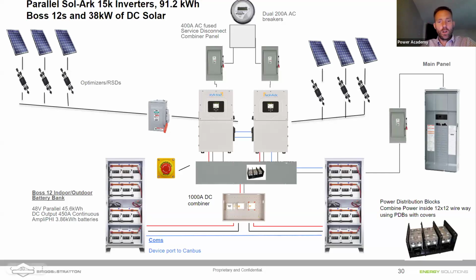I'm showing this here. We've got a 1,000 amp combiner that's here. Briggs & Stratton also offers our own 1,000 amp combiner. We'll have more products on the way. You could also use, for these batteries, you're not required to have overcurrent protection on them, and so you could use a power distribution block to combine inside the wireway. Do keep in mind, if you are doing a wireway underneath the Sol-Ark 15K, those units are about 12 inches deep, so you'll want to get a deeper wireway.